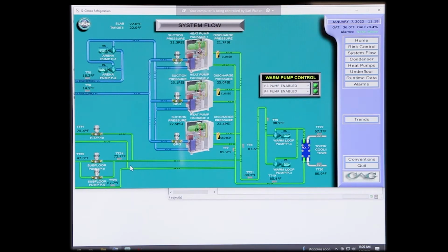I will tell you that if you happen to notice when the underfloor does call to start, and the underfloor currently is set at 40 degrees, and there's a sensor down in the subsoil. What's going to happen is there's logic in the program that's going to start looking at temperature sensors, because it's very important that we keep this whole warm loop warm, because that's what gives us our proper discharge pressures for the systems to run correctly. We've got programming in there now that will cycle the pumps, P8, P9. You're going to hear them start and stop, all based on maintaining a proper glycol temperature to keep the compressors running correctly. Because that underfloor has 500-600 gallons of cold glycol sitting under there at 40 some odd degrees. We don't want that 40 to come all in one shot into a 100-degree system and crash that glycol temperature, crash that discharge pressure. So we're going to cycle those.